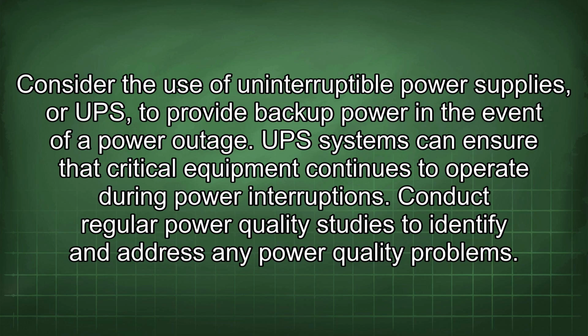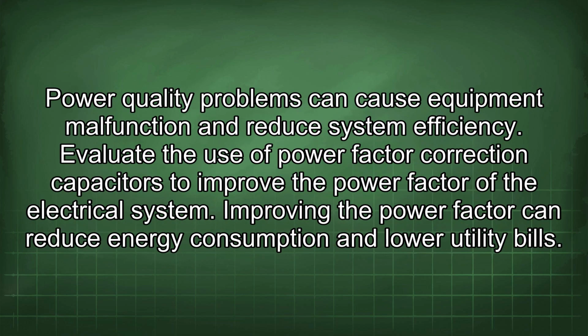Conduct regular power quality studies to identify and address any power quality problems. Power quality problems can cause equipment malfunction and reduce system efficiency. Evaluate the use of power factor correction capacitors to improve the power factor of the electrical system. Improving the power factor can reduce energy consumption and lower utility bills.